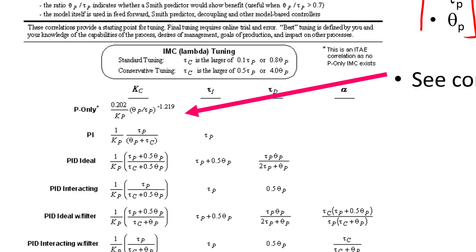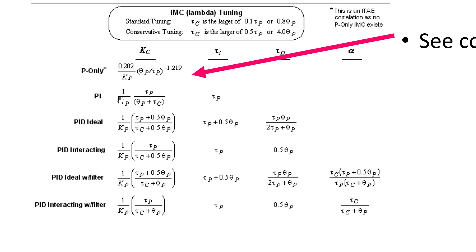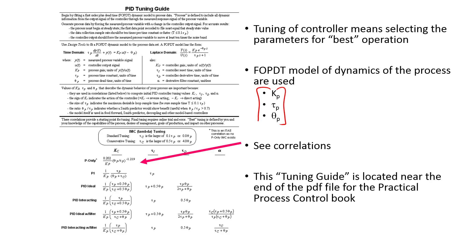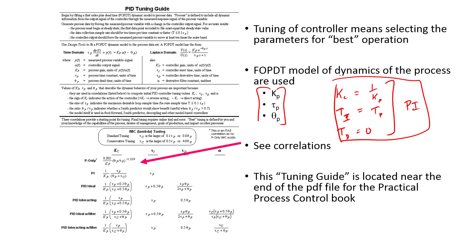Zooming in on the IMC tuning correlations, you can see that k_p, tau_p, and theta_p feed into the correlations to give good starting points for the controllers. One tuning guide I like: k_c equals 1/k_p, tau_i equals tau_p, and tau_d equals 0. This is a PI controller that often does very well. You can also use IMC or ITAE correlations, which are very popular.